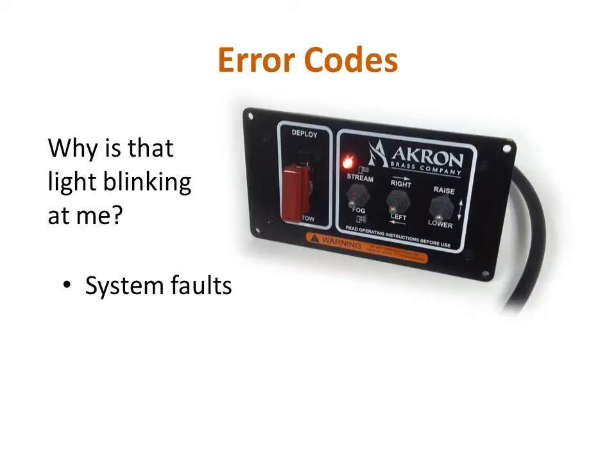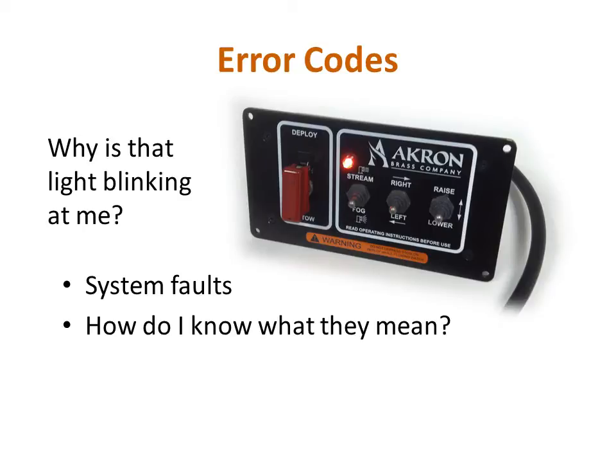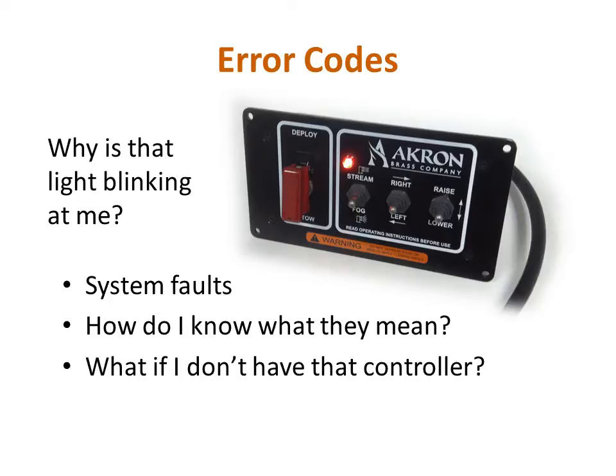I'm not going to list them specifically here, but they generally cover problems such as not registering a sensor or the monitor not being able to reach its intended stow or deploy position. They are listed individually with descriptions and suggested fixes in the DeckMaster installation, operation, and maintenance instructions available on the Akron Brass website. If you are using a system that only includes a tether controller and a separate switch for stow and deploy, but does not include an indicator light, you will need to remove the cover from the logic box and look at the LEDs on the circuit board to see any error codes that are being displayed.